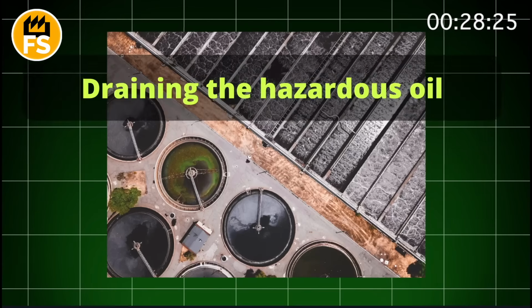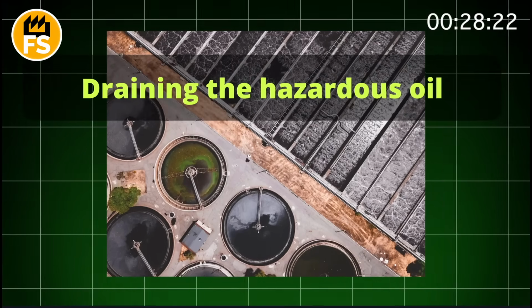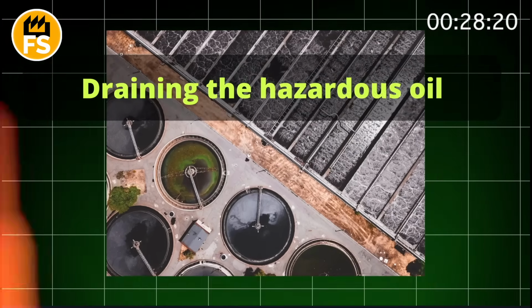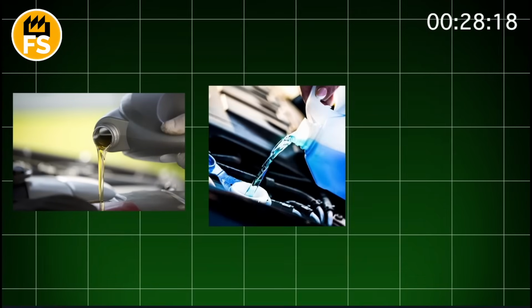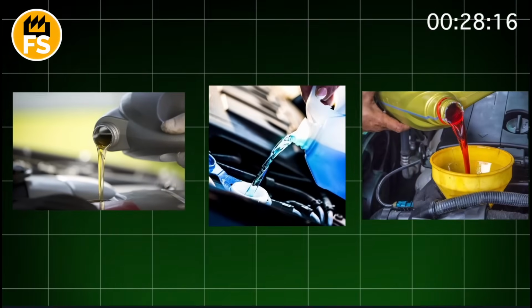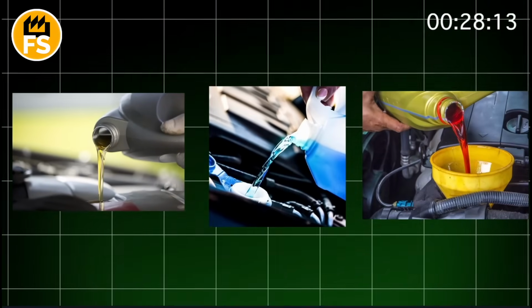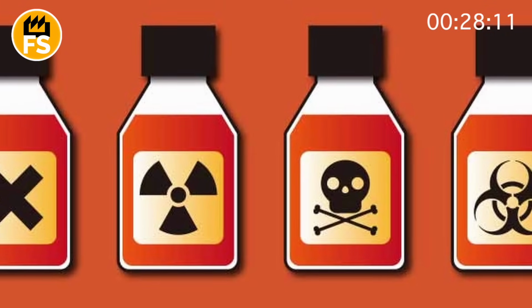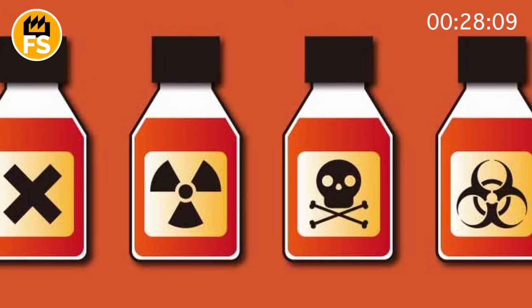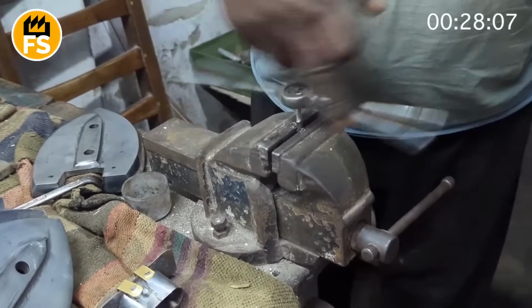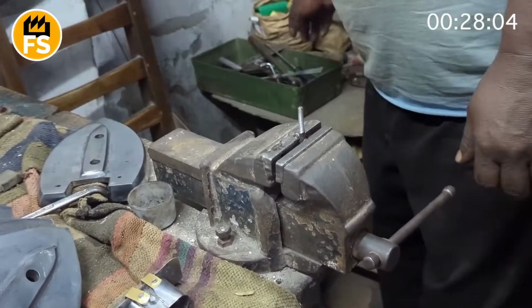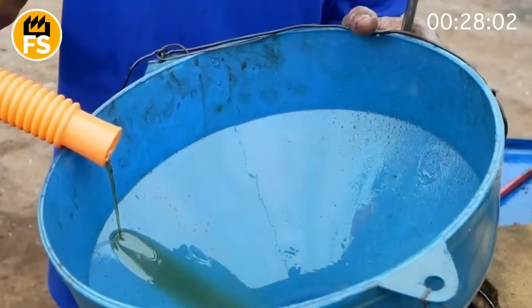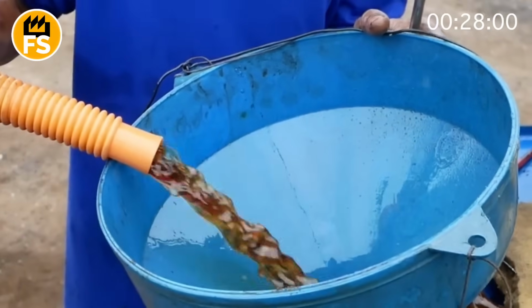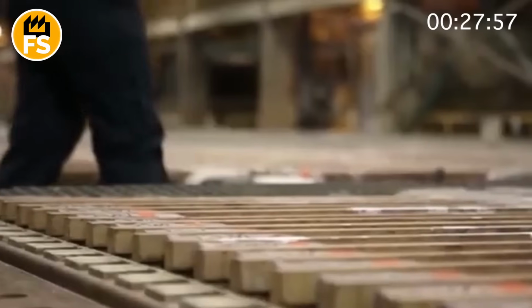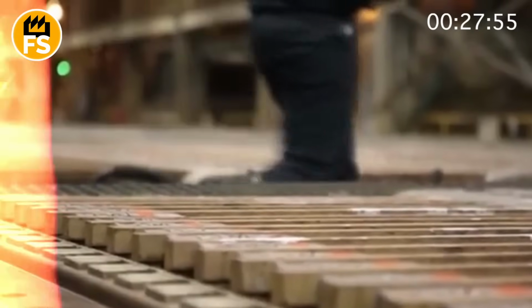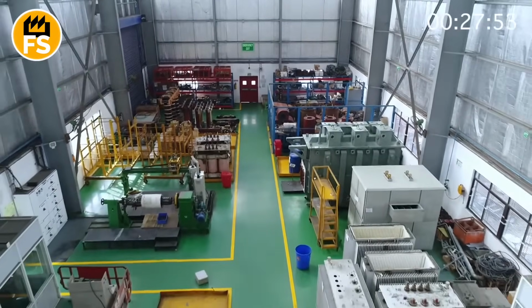Draining the hazardous oil is a highly precise, high-containment operation, executed with surgical care. Transformers are carefully positioned over multi-layered sealed collection systems, often including large secondary containment basins designed to catch any potential leaks or spills, no matter how small. Workers use specialized pumps, leak-proof fittings, and designated tools to access drain valves and carefully remove every single drop of the hazardous oil directly into secure, heavy-duty, properly labeled tanks.